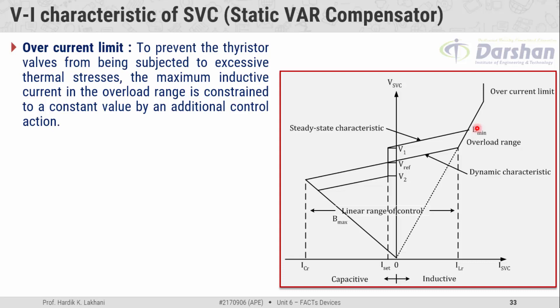The overcurrent limit: to prevent the thyristor valves from being subjected to excessive thermal stress, the maximum inductive current in the overload range is limited to a constant value by additional control action. In order to protect the components of the SVC compensator, the maximum inductive current in the overload range is limited to a specific constant value, and that portion is known as the overcurrent limit.